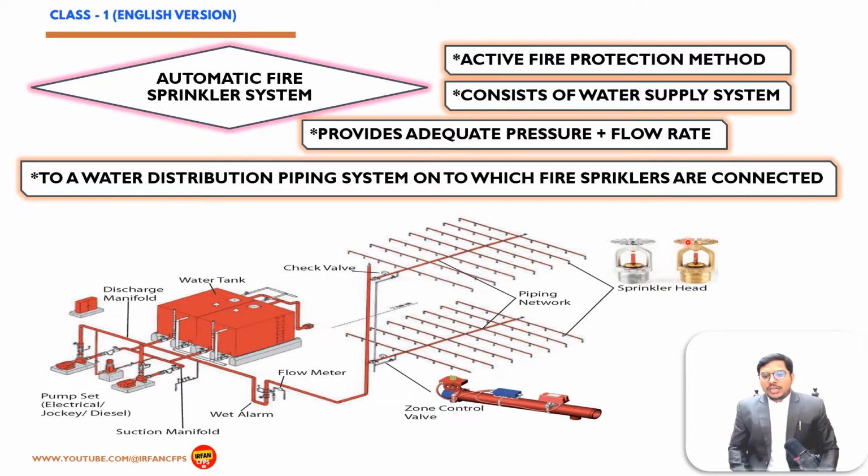During fire conditions, the heat sensitive liquid in the glass bulb expands, causing the glass to shatter, releasing the pip cap and sealing spring assembly. Water flowing through the sprinkler orifice strikes the sprinkler deflector, forming a uniform spray pattern to extinguish or control the fire.